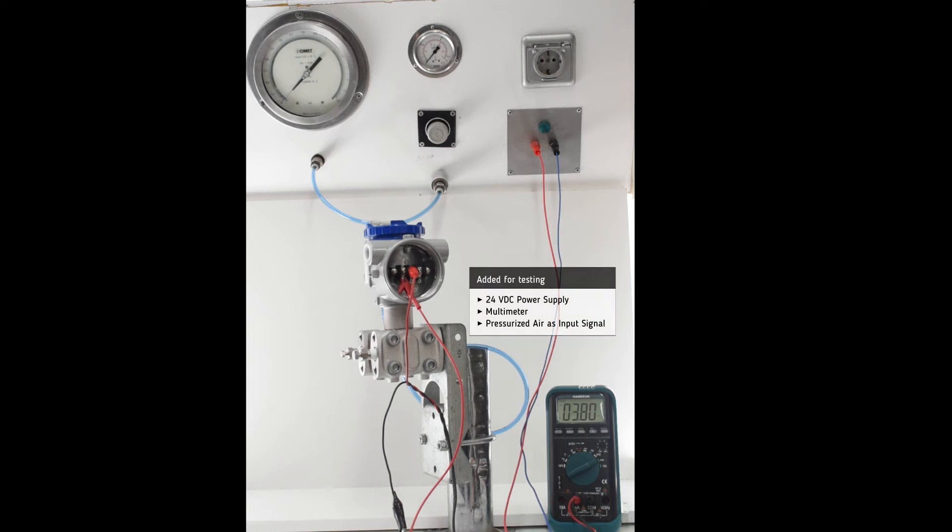For testing, we add a 24 volt DC power supply, a multimeter in order to measure the milliamp output, and some pressurized air as input signal.